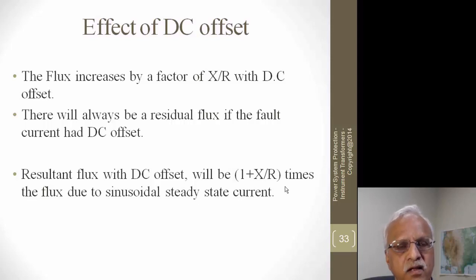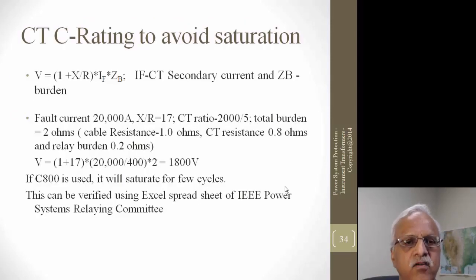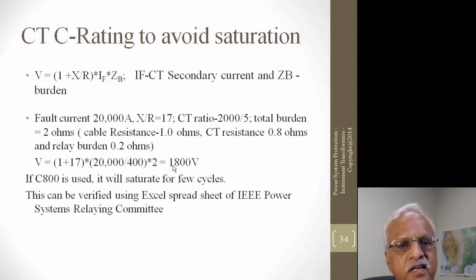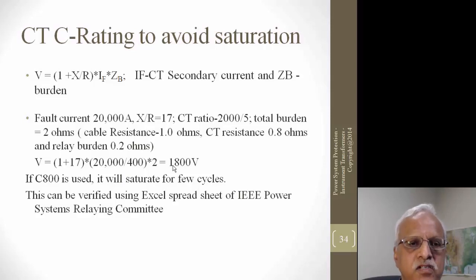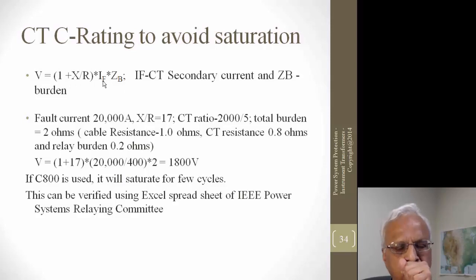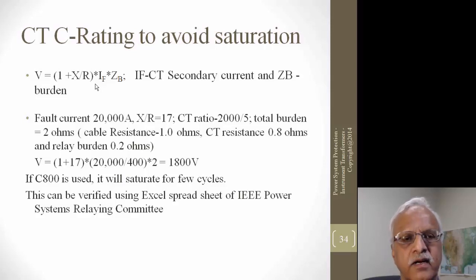As an example: fault current is 20,000 amps, X/R is 17, CT ratio is 2000:5, and the burden (cable resistance plus CT winding) is 2 ohms. The voltage that develops across the secondary is 1800 volts — if the CT is only rated for 800 volts, it saturates within a few power cycles. To avoid saturation, you need the fault current to be less than the C rating divided by the burden times (1 + X/R), or reduce the burden to minimize the likelihood of saturation.